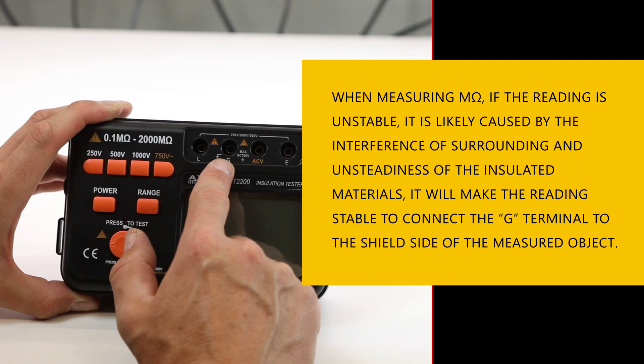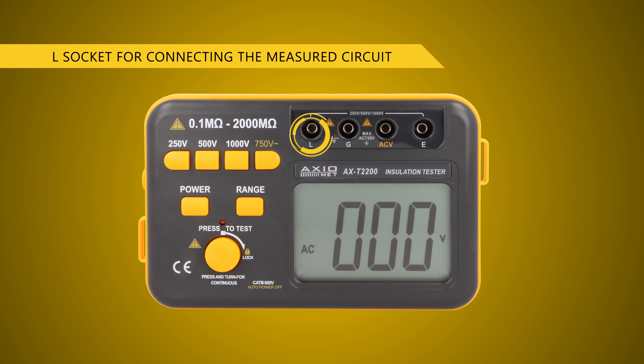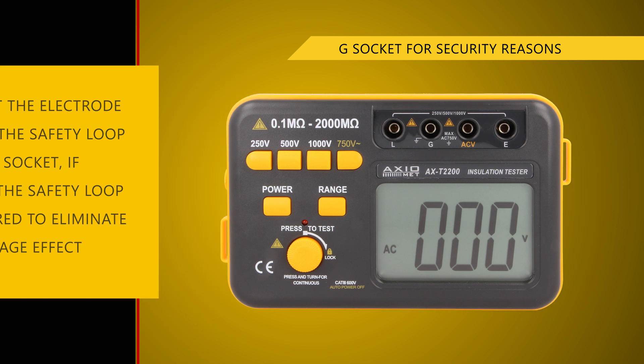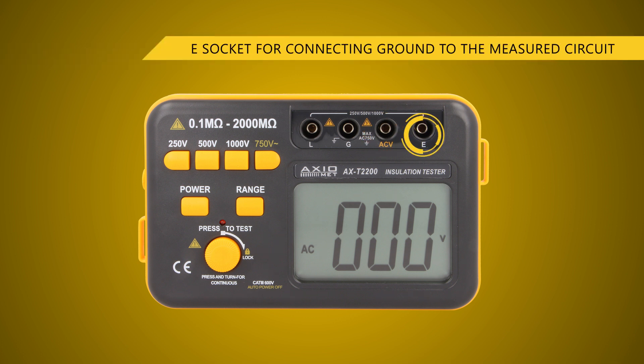The ohmmeter is equipped with four sockets. They help to perform three-wire measurements, which are needed in the case of big devices, and help to eliminate the influence of surface leakage current on the result. The fourth socket is used to measure alternating voltage up to 750 volts AC.